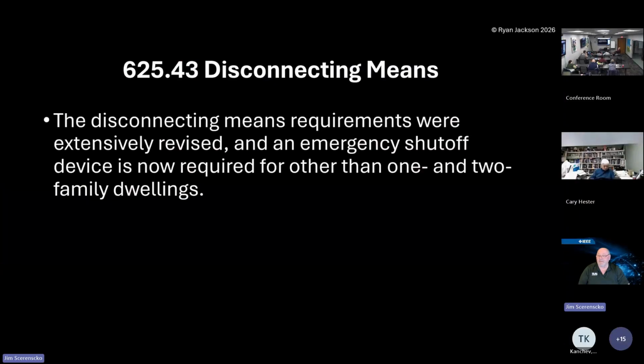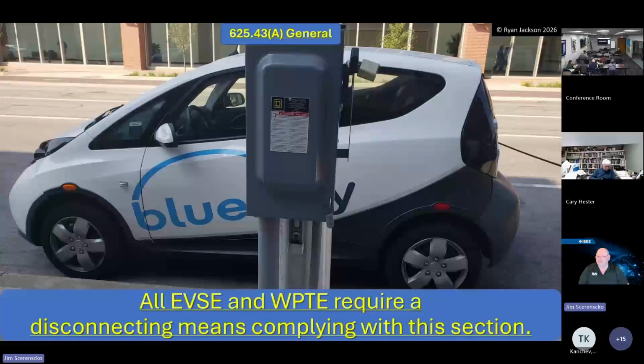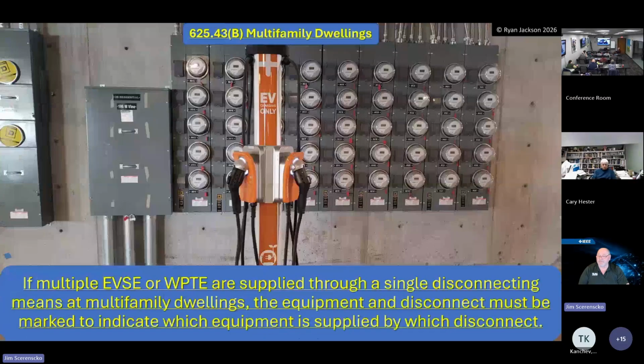And then it goes on and on about this. The disconnecting means is required in complying with this section. You have to have a disconnecting means for the EV chargers. If you have multiple EVSEs or WPTEs supplied by a single disconnecting means at multifamily dwellings, the equipment and disconnect must be marked to indicate which equipment is supplied by which disconnect.